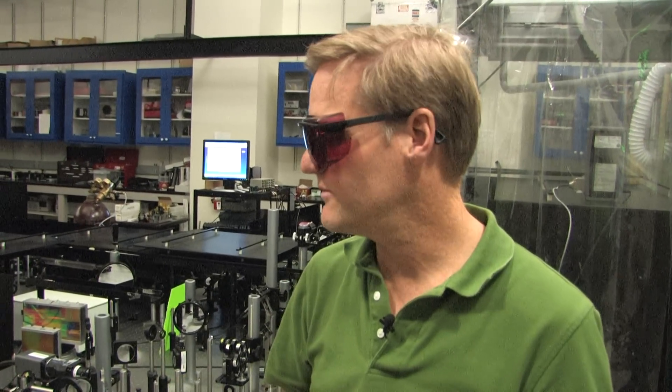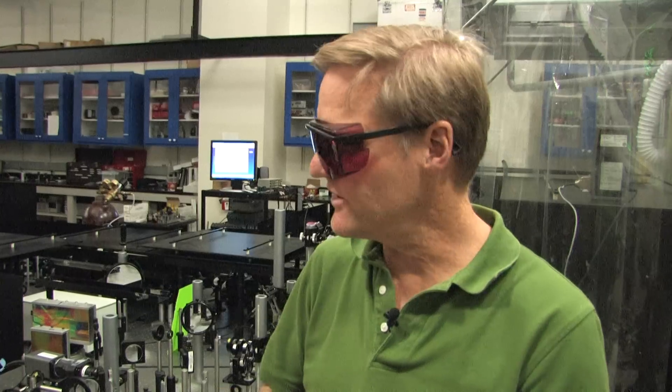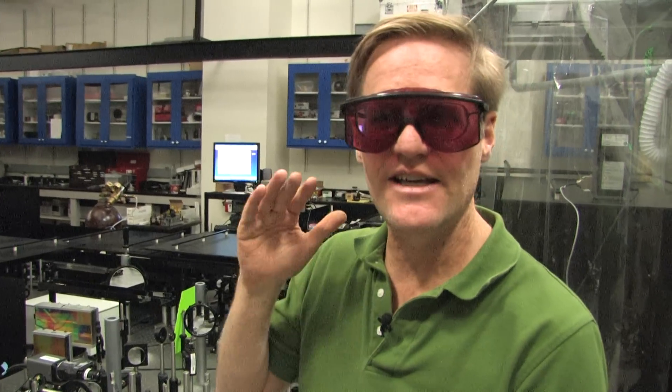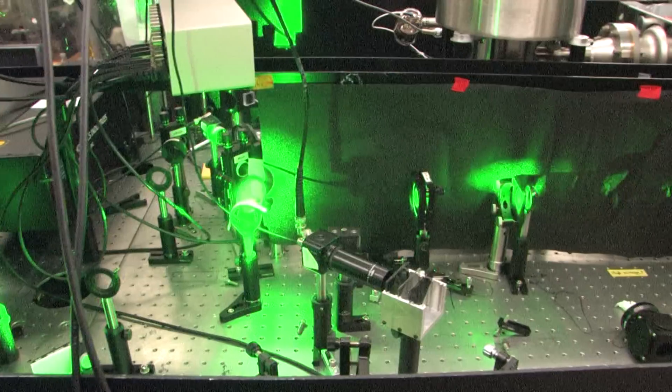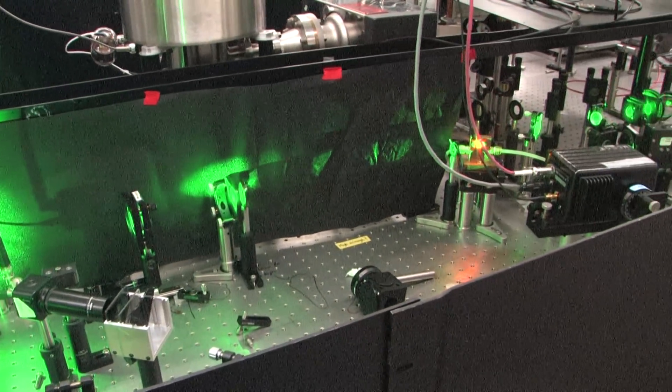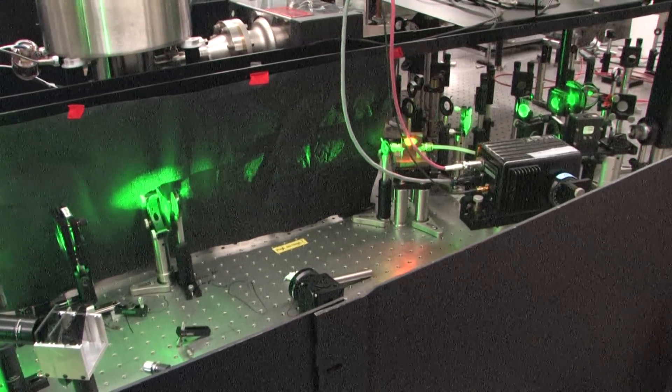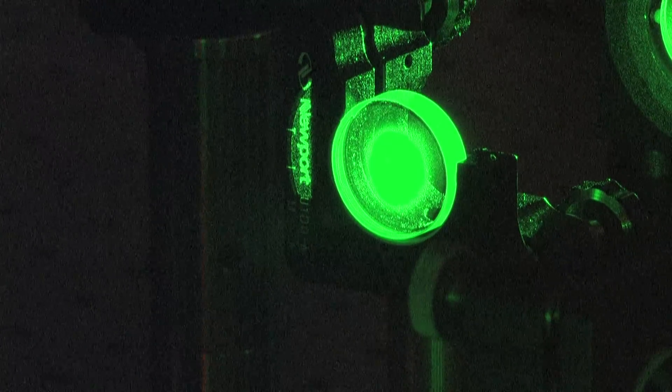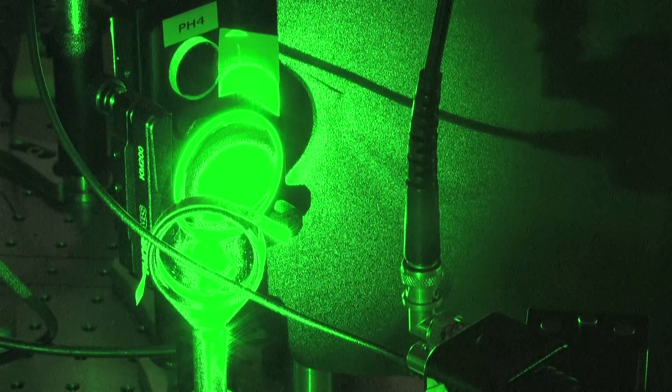With a femtosecond laser the ablation is entirely deterministic. The intensity is so high, it's what we call plasma mediated ablation. The energy is absorbed and you just ionize and lift off a perfect layer so there's no thermal damage zone. That enables us to make these devices with extreme precision. We can actually make nanostructures with this type of femtosecond micromachining.